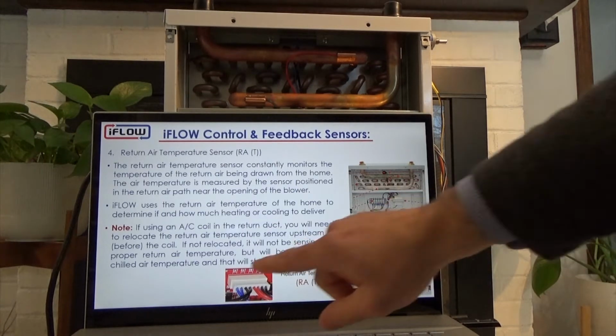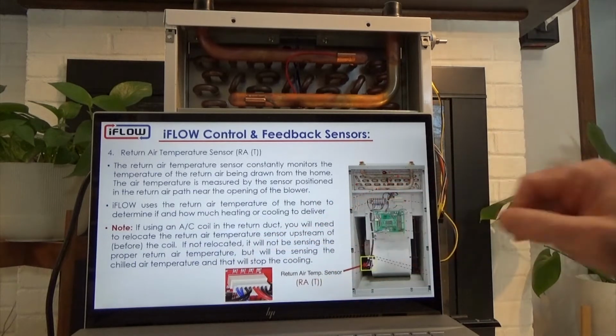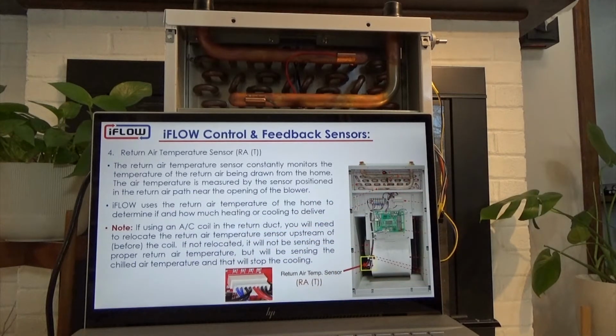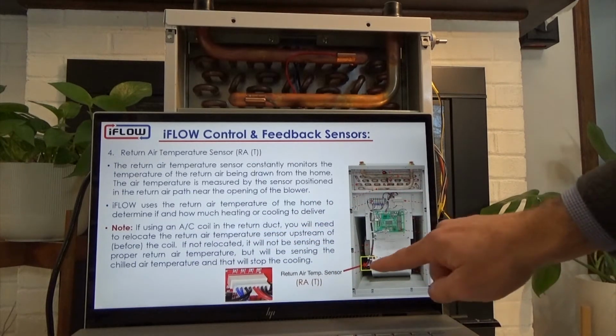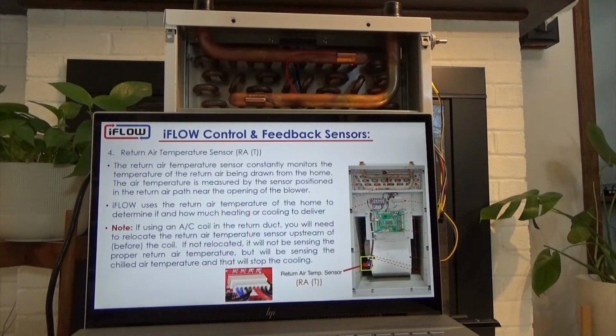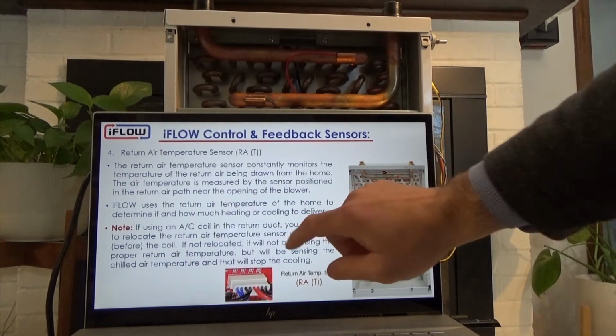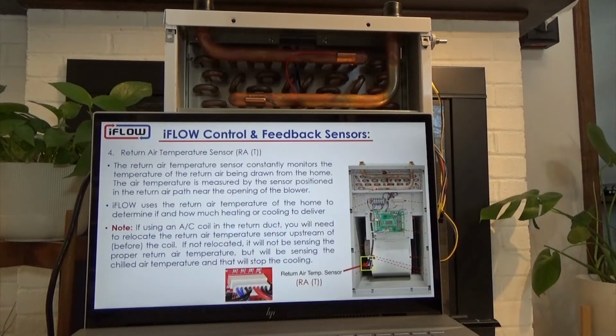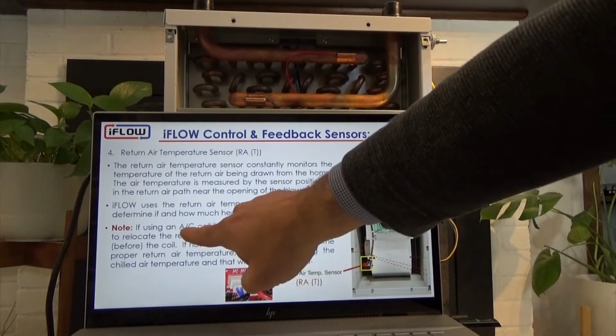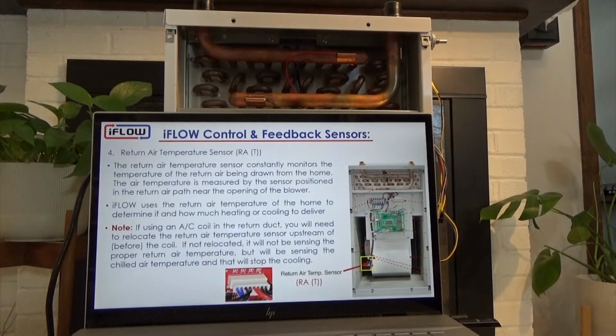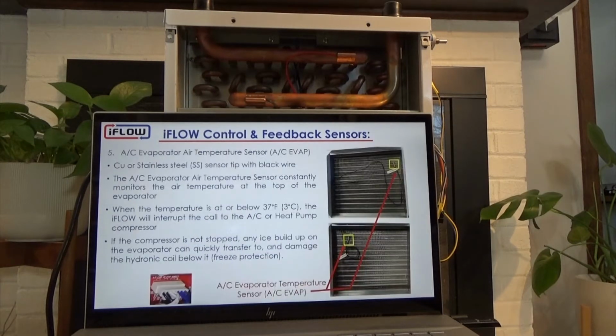Just one note, and we'll look at this a little further. If you're using an AC coil on the return, then we will need to relocate the return air sensor upstream of that. We'll look at that more closely with some diagrams to solidify the point, but I mention it here: if you're using an AC coil on the return duct, you'll need to relocate that return air sensor.